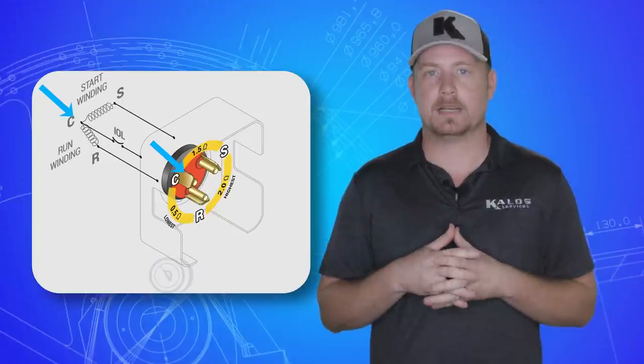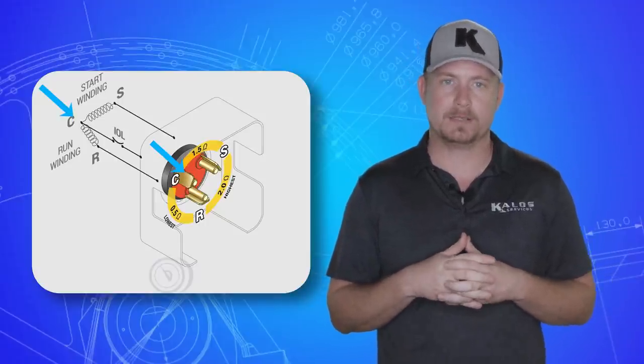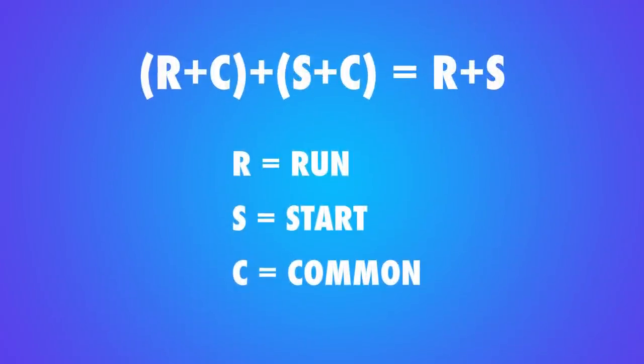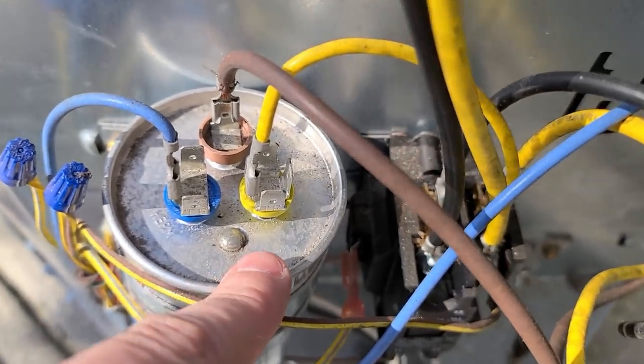In the compressor, it's the common point between the run and start windings. This is why R plus C plus S plus C equals R plus S. If you ohm a compressor, the C terminal of a dual capacitor is actually fed from the opposite leg of power as the C terminal on the compressor.